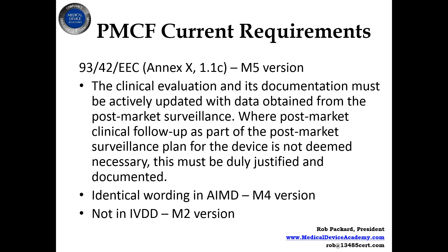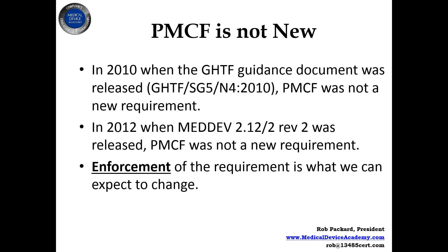This next slide shows you what the post-market clinical follow-up current requirements are. I give the reference to the regulation — it's 93/42/EEC, Annex 10, 1.1c. I also indicate where the requirements are in the AIMD. The IVD doesn't have it, but I indicate later in the presentation where it is in the new regulation. So this covers both old regulations and proposed regulations that will be released in 2016, if not sooner. I also point out that none of these requirements are new — it was in existence prior to 2010. It was in the guidance document in 2010 put out by the Global Harmonization Task Force, and they released a MEDDEV that would be a formal guidance in 2012. The enforcement of it is what's new.